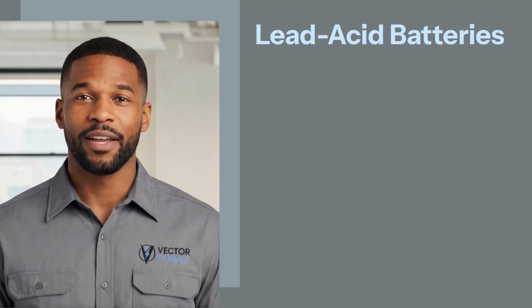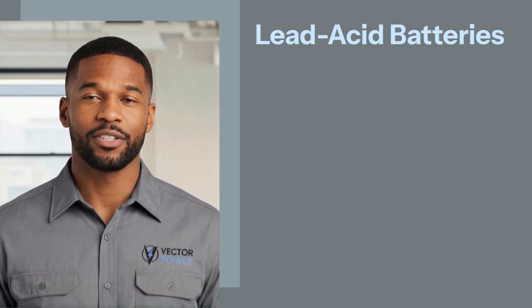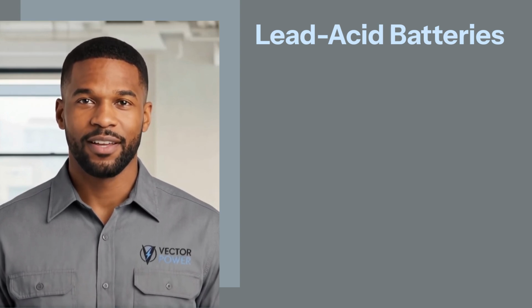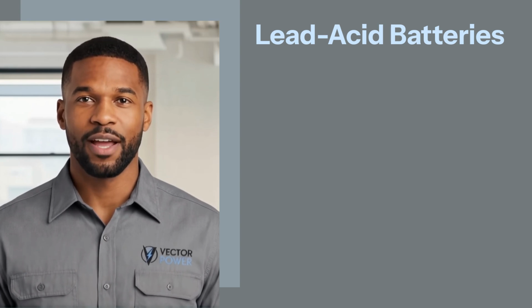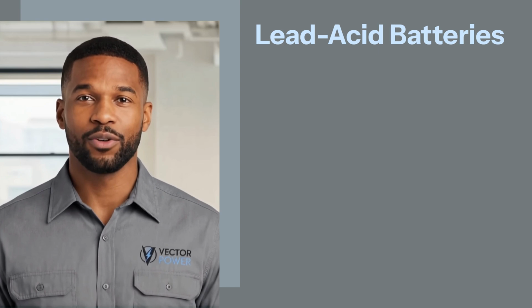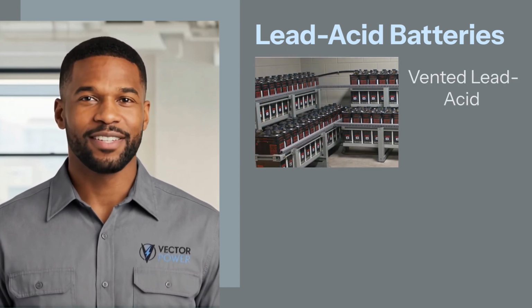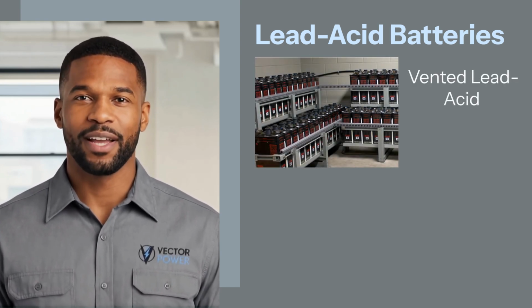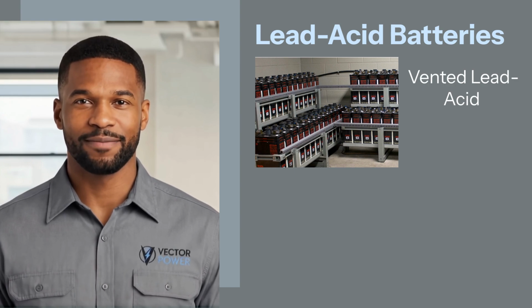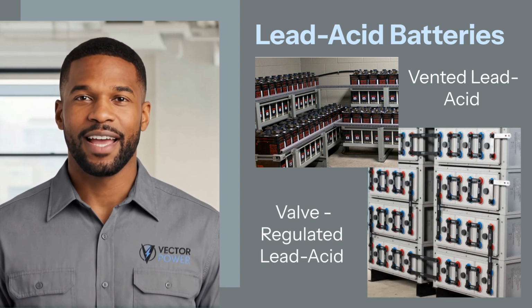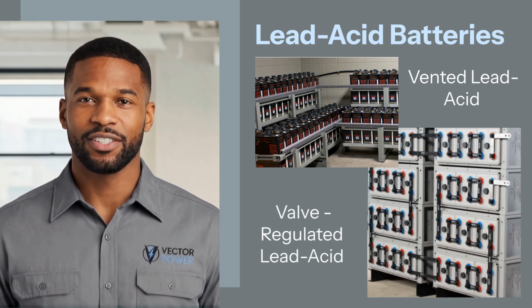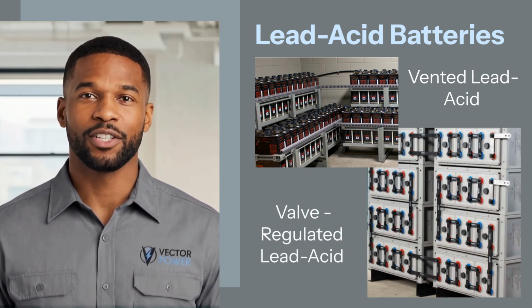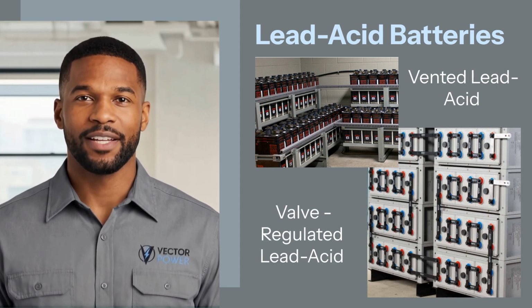Lead-acid batteries remain the most mature and widely used stationary energy storage technology. They are commonly found in UPS systems, telecommunications infrastructure, and power substations. Key types include flooded or vented lead acid, which requires periodic maintenance, including electrolyte level checks, and valve-regulated lead acid, sealed designs such as AGM, absorbed glass mat, and gel batteries that offer lower maintenance requirements.